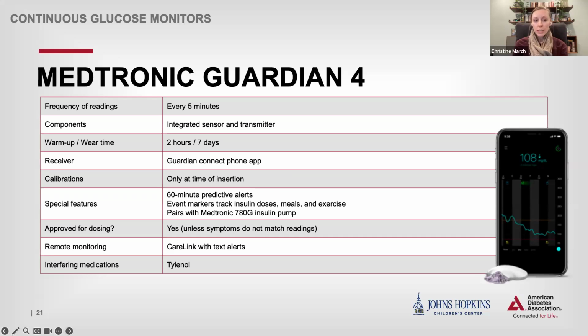The Guardian 4 was recently released and is definitely an improvement upon the Guardian 3. This is also an integrated sensor transmitter with no change to the warm-up time or wear or receiver. The calibrations, though, are only at the time of insertion and are not required subsequently unless prompted. This one will pair with the Medtronic 780G insulin pump, which is their newest among the automated insulin delivery systems. And unlike the Guardian 3, it is FDA approved to use this device to dose insulin, unless, of course, symptoms don't match readings. Otherwise, the CareLink and the Tylenol are the same.